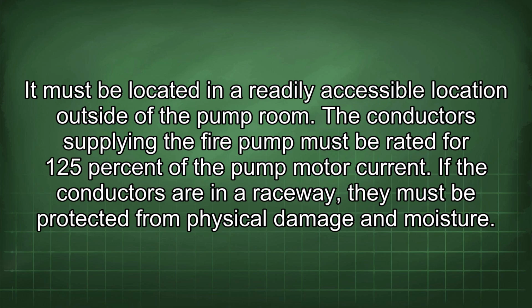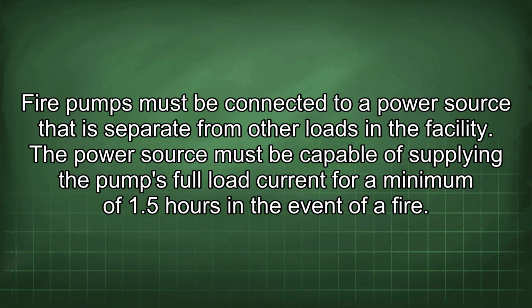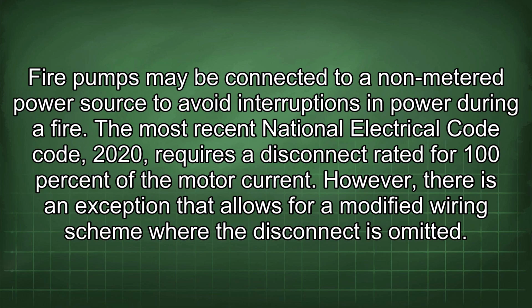The conductors supplying the fire pump must be rated for 125% of the pump motor current. If the conductors are in a raceway, they must be protected from physical damage and moisture. Fire pumps must be connected to a power source that is separate from other loads in the facility. The power source must be capable of supplying the pump's full load current for a minimum of 1.5 hours in the event of a fire. Fire pumps may be connected to a non-metered power source to avoid interruptions in power during a fire.